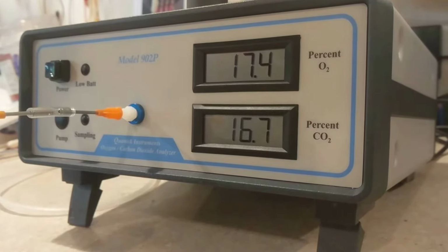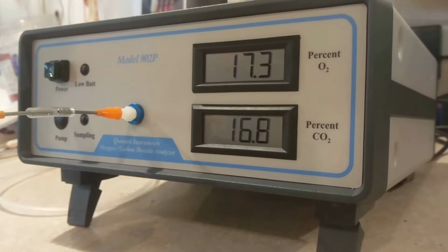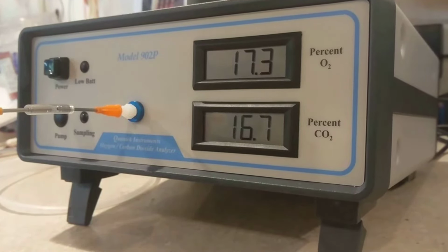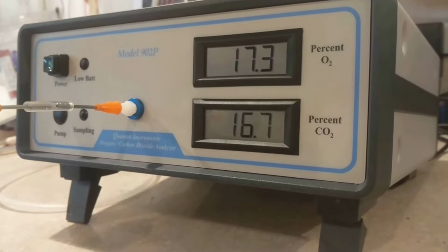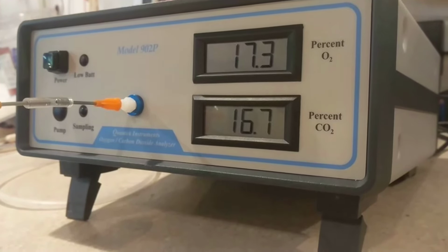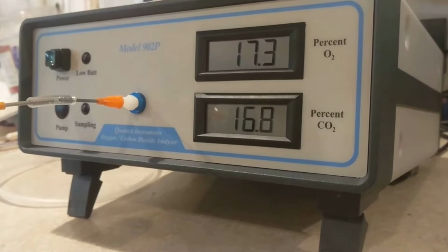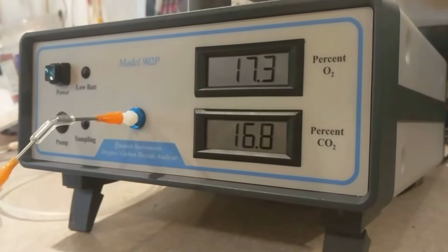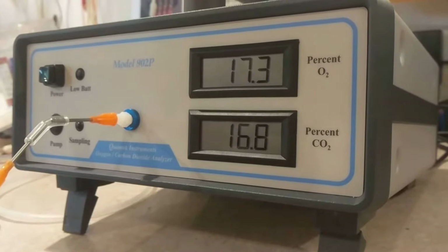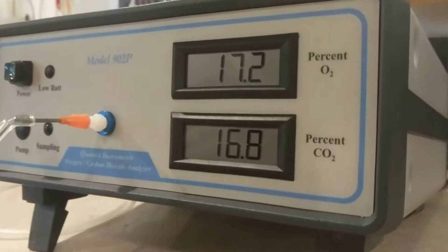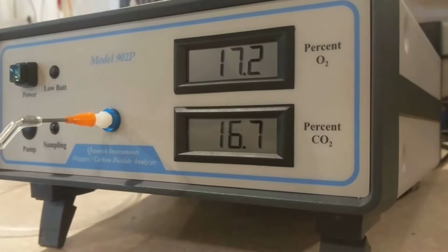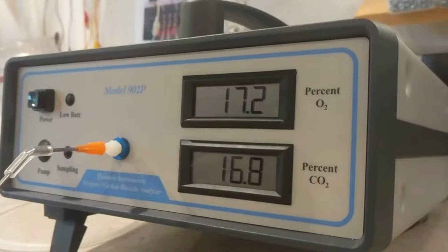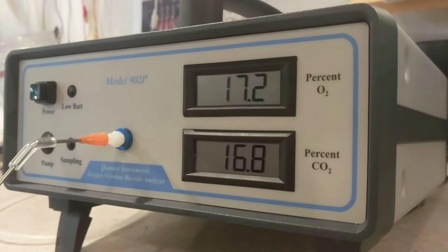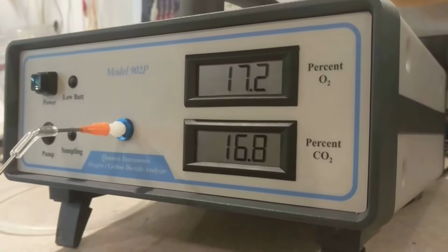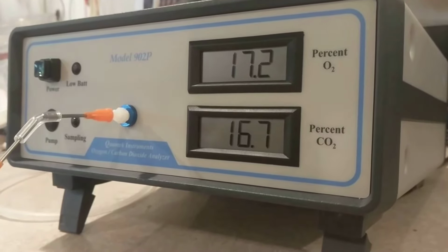And so that looks pretty stable. We end up with 16.8, and the sensor is a little bit pressurized as I am injecting the gas. As you can see, it's not really going to change much, and it'll probably drift down a little bit as I stop plunging gas in. And so this verifies that we're pretty close on the 16%, 16.7. And the oxygen is 17.2, which should represent 5/6 of 20.9%.